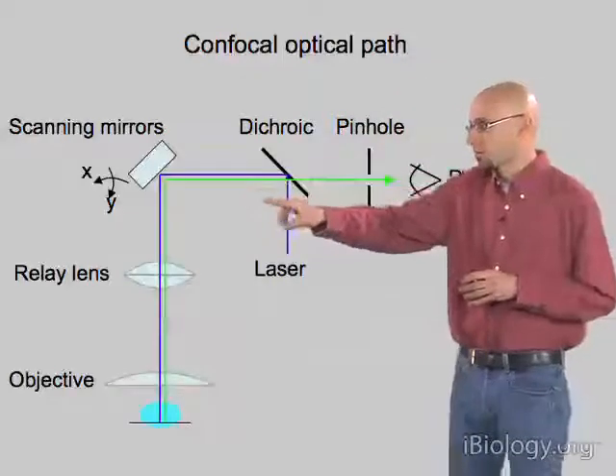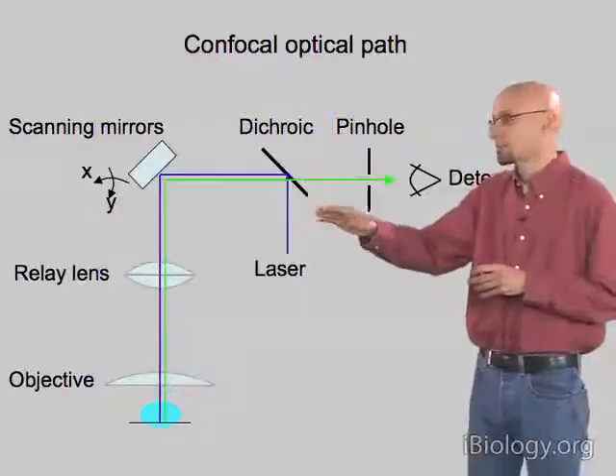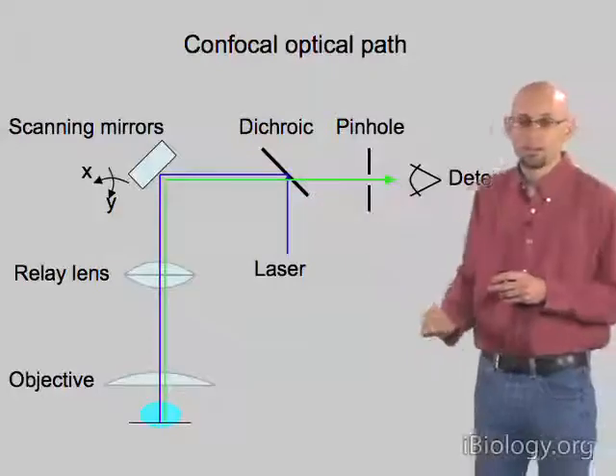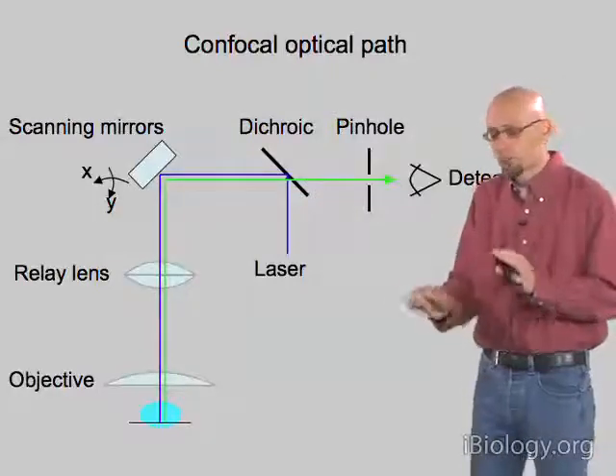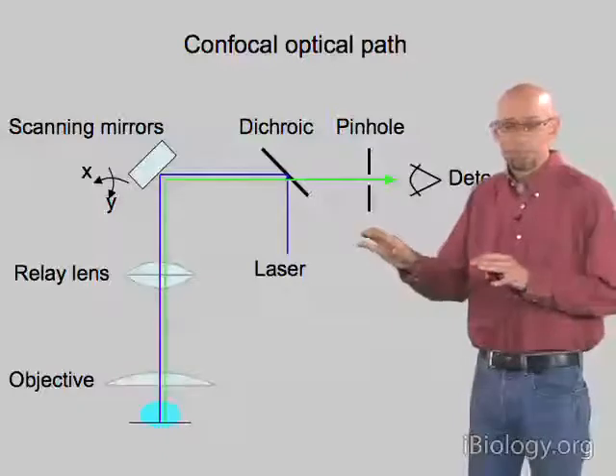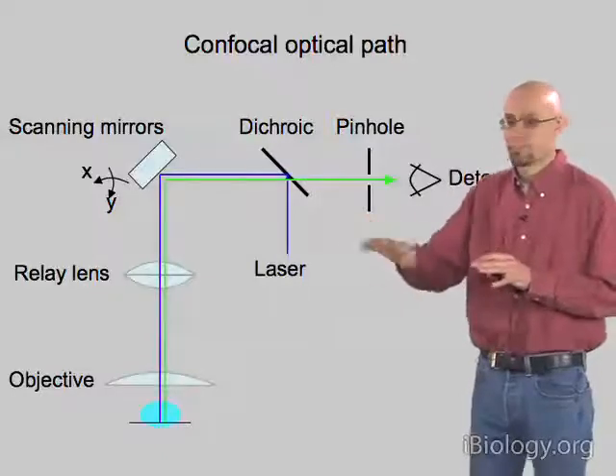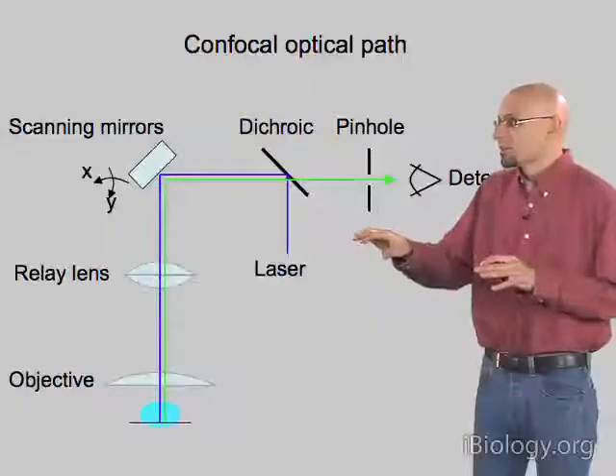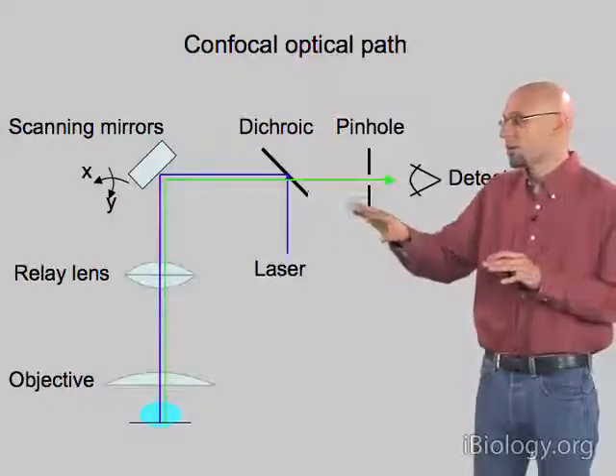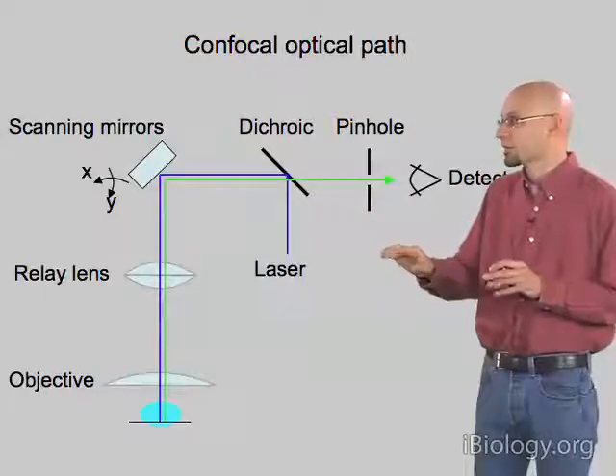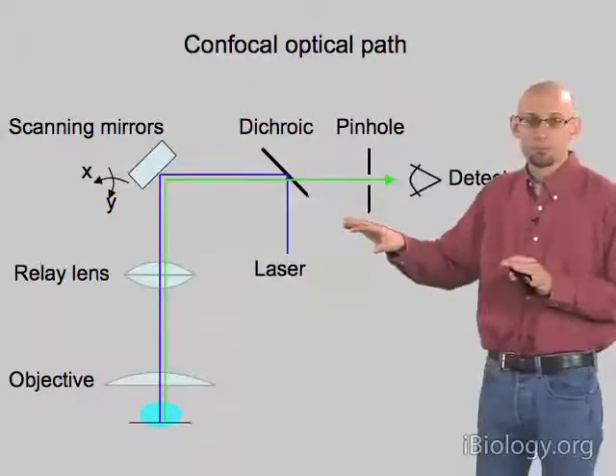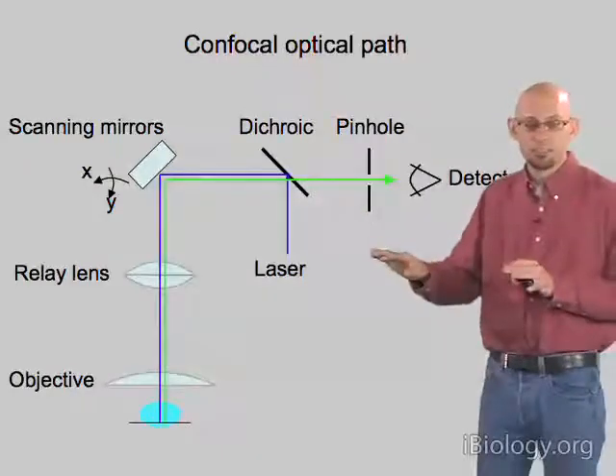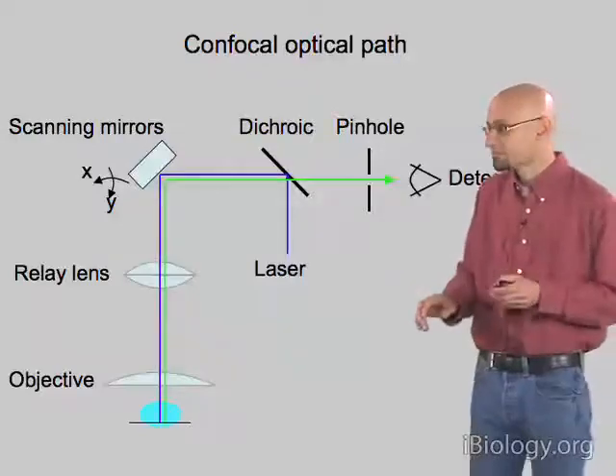All we need is a dichroic mirror — this 45-degree mirror — which separates the emitted light from the laser. We can then pass that through our pinhole, and it will reach the detector regardless of where it came from on the sample. By using the same pair of scanning mirrors twice — once to scan the illuminated light, and a second time to de-scan the emitted light — we can keep our pinhole fixed. The emitted light will always come back along the same path regardless of where it came from in the sample. So we just have a single fixed pinhole, put a detector behind it, and we can see the emitted light regardless of where it came from.